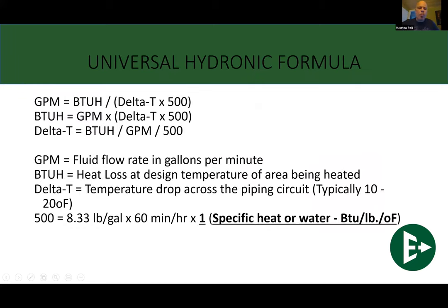Now we're going to be getting into a bit more of the basic formulas. Again, this is going to come out in the PDF that you're going to get from your local Equipco rep. These are just formulas that we need in the system with regards to how to size different things. I talked about before, you need the proper BTUs to heat a room. In order to do that, you've got to hit the proper GPM flow rate to get to the temperature you're looking for, and then the delta T, of course being your temperature differential. We have something in the hydronics industry called the Universal Hydronics Formula.